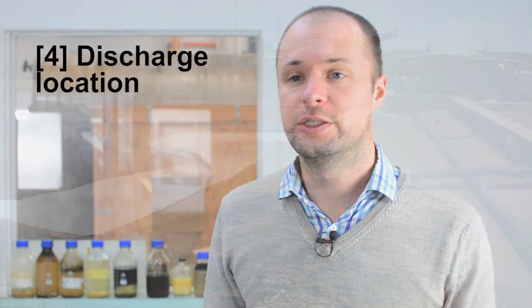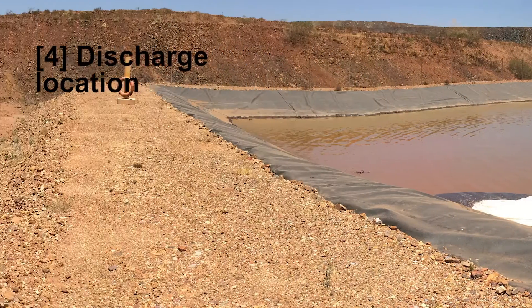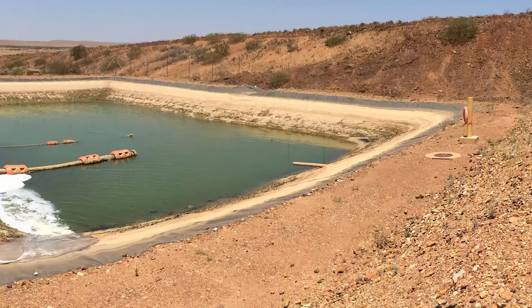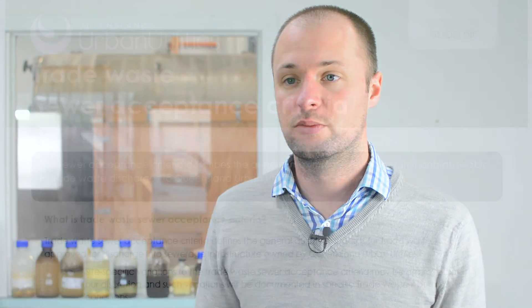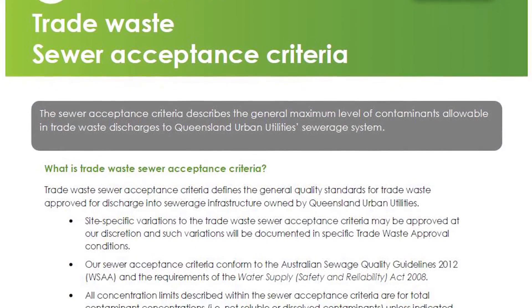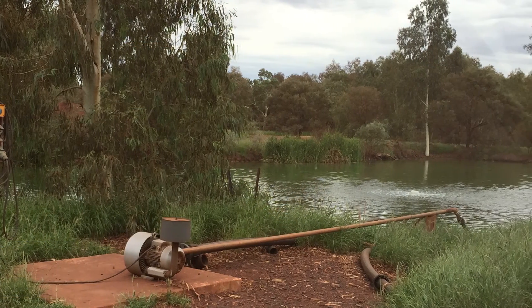Another factor that we consider is the discharge location. The discharge location dictates what quality of water you're going to need to produce from your oily water separator. For example, if you're sending your water straight to the sewer then that requires a lower quality of water to comply with the regulations. But if you're trying to send treated water to a river, straight to the environment, that's going to require a much higher quality of water and therefore a much more powerful separator.